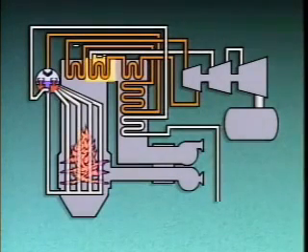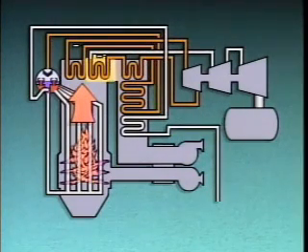The secondary reheater in this example can also be classified as a radiant reheater because it's located in a line of sight with the boiler flames and receives most of its heat by radiation from the flames.